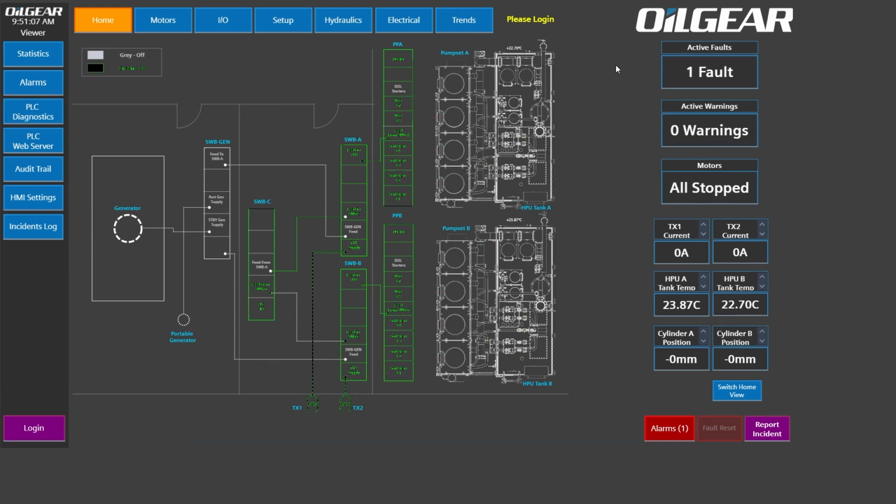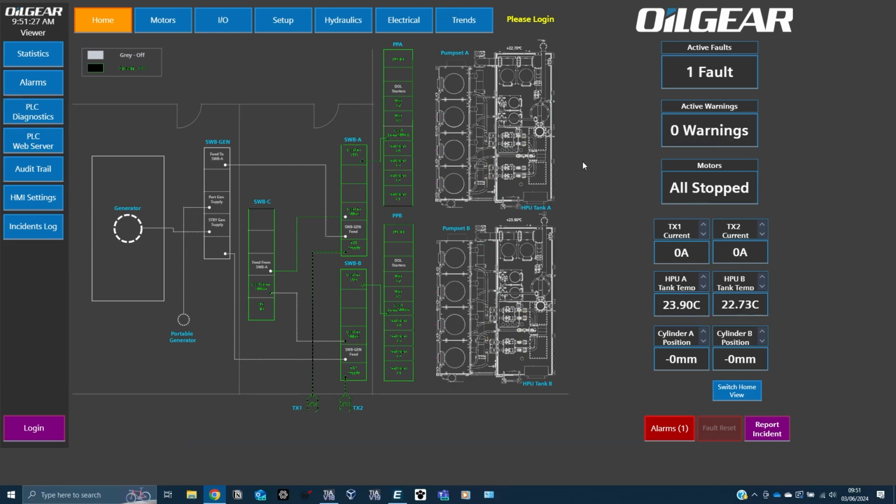And then I immediately flashed back to all the other systems I've seen with all these invisible buttons somewhere. So now essentially anybody at any time can just walk in, click that button, and now they have full access to the entire system, which is just insane. So what I did at that point then is I said, how can I stop all these things from happening? And then I just randomly came up with this idea of a commissioning bit.